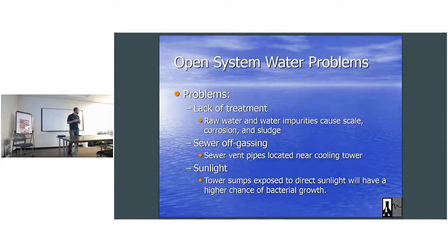There's one of those strainers. This is on that Climacool? One of them. Gross. That's pretty nasty. That one was. Well, that's just a product of putting a new piece of equipment on a crappy old loop that hadn't been cleaned out. And you said U.S. Water tried to clean it and didn't get it all?